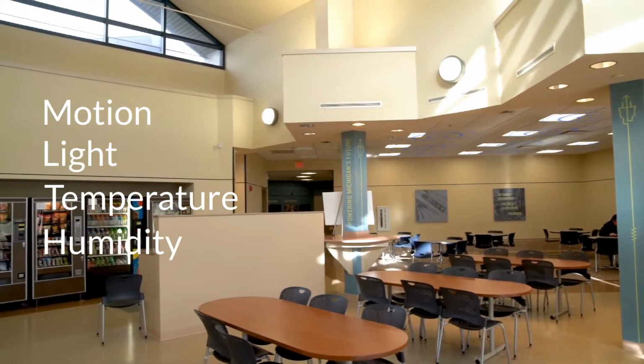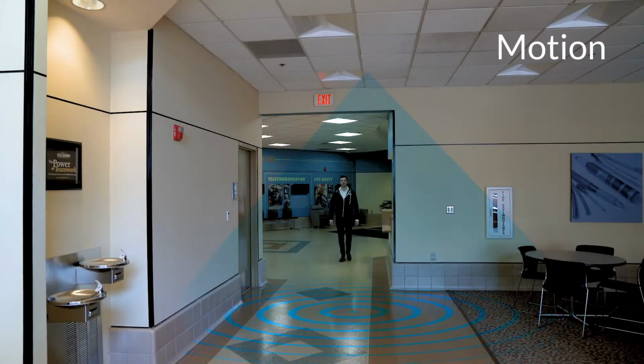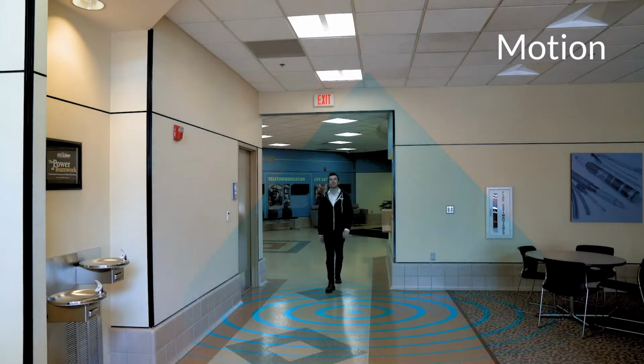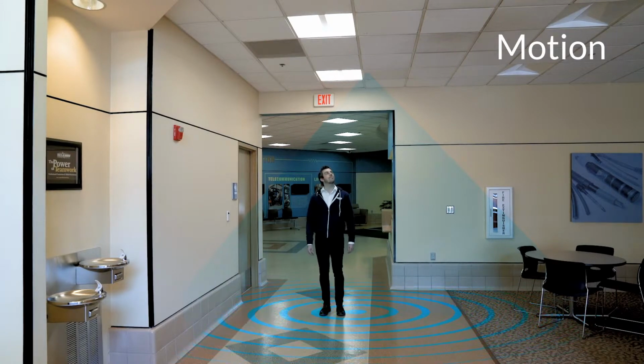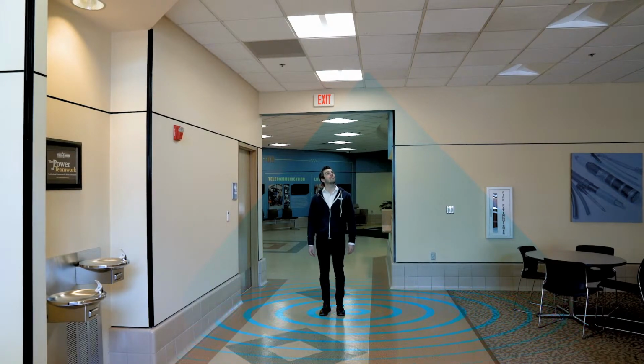The first is motion sensing, which is used to determine occupancy. The passive infrared motion sensor, located in the center of the sensor, detects motion through movement of objects that are a different temperature than the surroundings, like people. It uses 64 sensing elements, all aimed down out from the center at a 45-degree cone shape. If a person moves from one zone to another within the 64-zone grid, the sensor will detect motion.